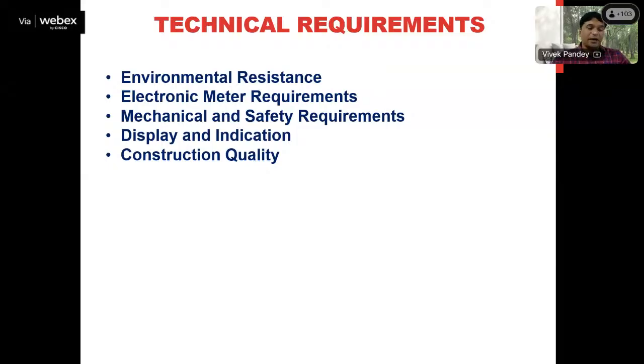Next technical requirement is related to the electronic meter requirement. So suppose electronic type meters are there. What requirements should they fulfill? The first requirement related to electronic meters is the power failure. Suppose there is a sudden power failure in the industry during the operation of the gas meter. During power failure, whether the gas meter is able to store the last data and display the last reading or not, this should be tested. It is not that a sudden failure happens and the previous data vanishes. So it should be tested in the electronic meter requirement.